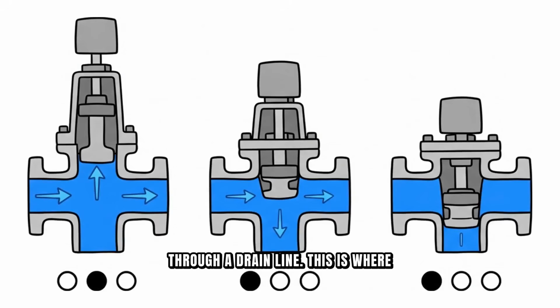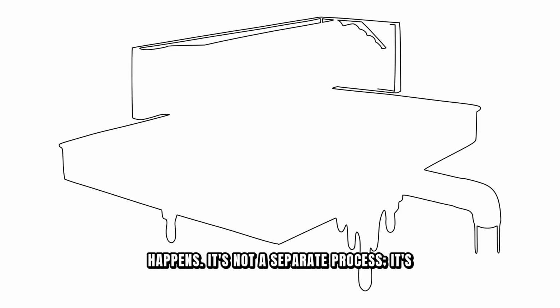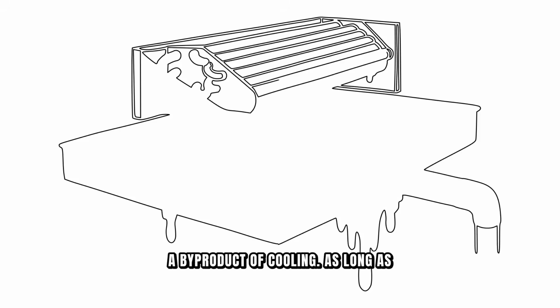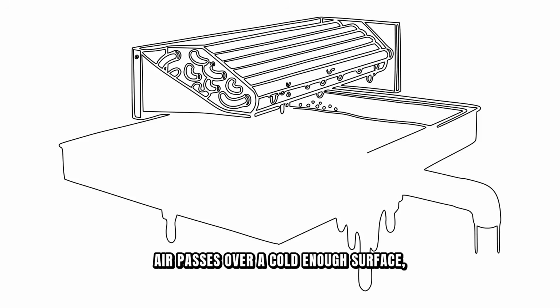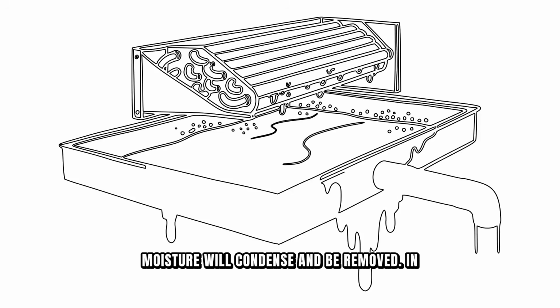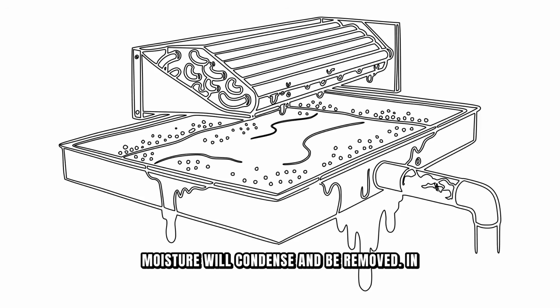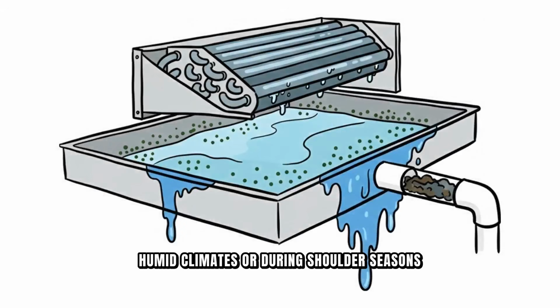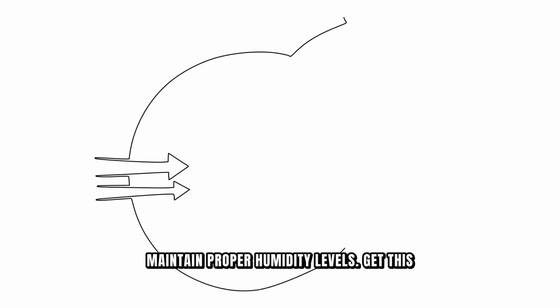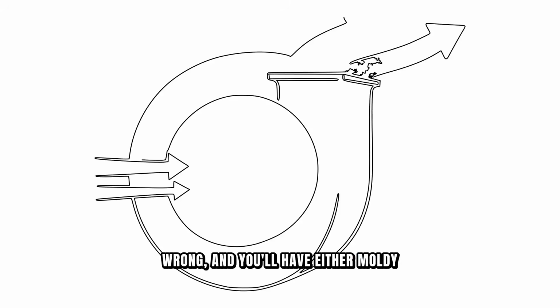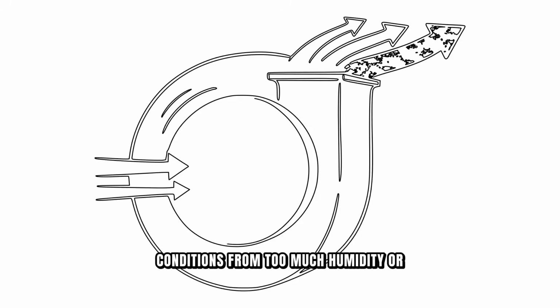This is where dehumidification happens. It's not a separate process. It's a byproduct of cooling. As long as air passes over a cold enough surface, moisture will condense and be removed. In humid climates or during shoulder seasons, when you need cooling but not maximum cooling, the chilled water valve modulates to maintain proper humidity levels. Get this wrong, and you'll have either moldy conditions from too much humidity or uncomfortably dry air.